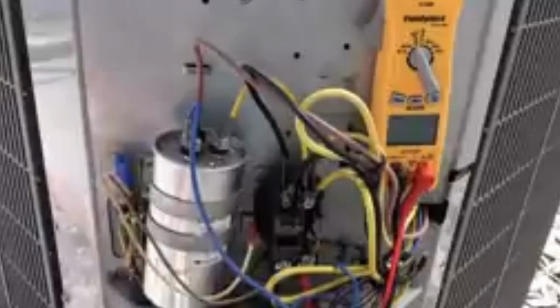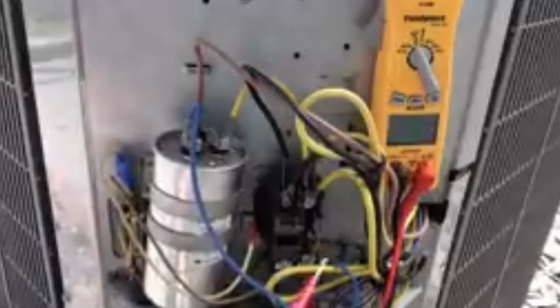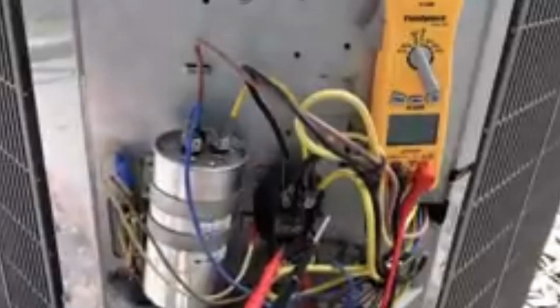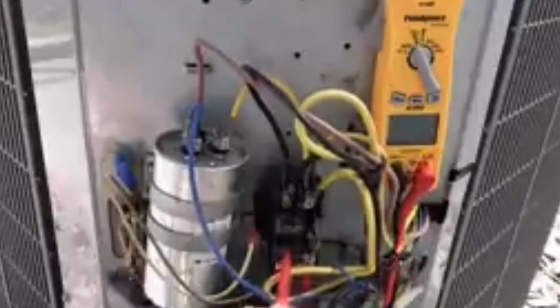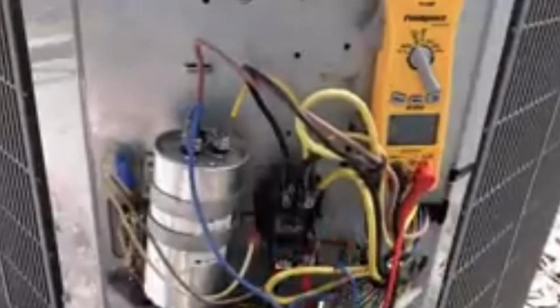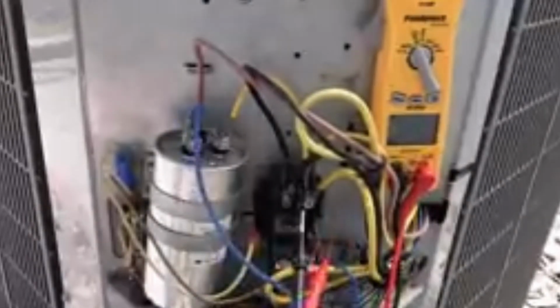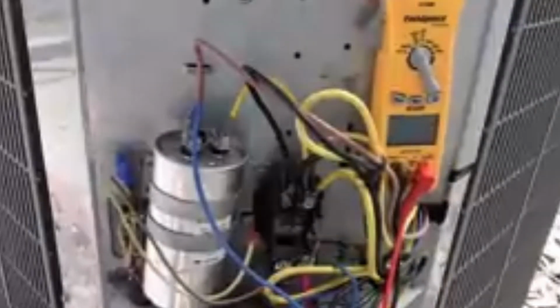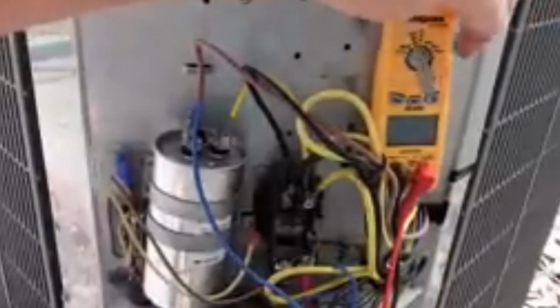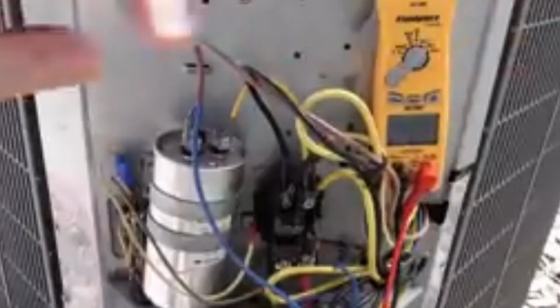Just to identify quickly the components that we're looking at right now, this is the contactor, which is our main switch, and as you can see, it's already pulled in by a 24-volt electromagnet on the underside, which means that we have 24 volts applied across our contactor. This comes from our inside transformer and thermostat.